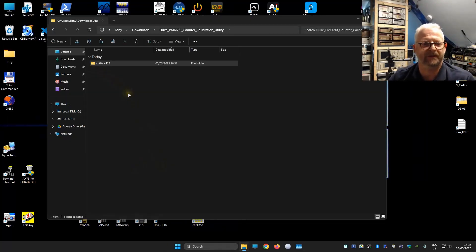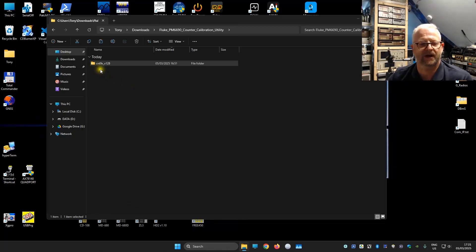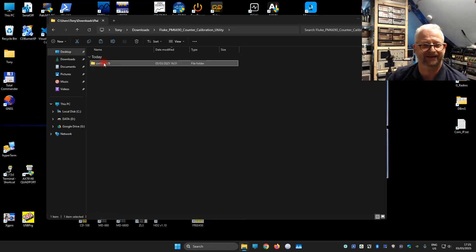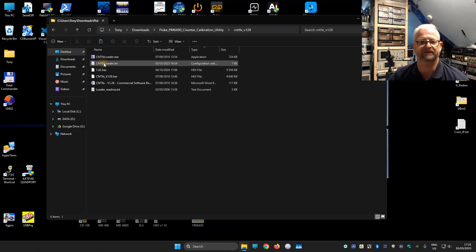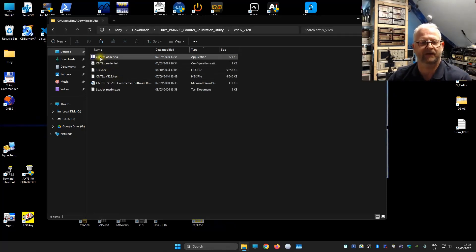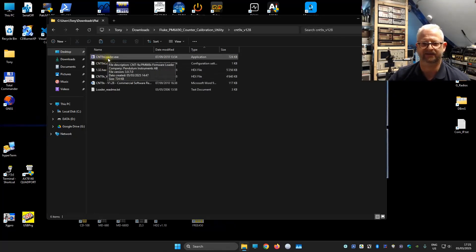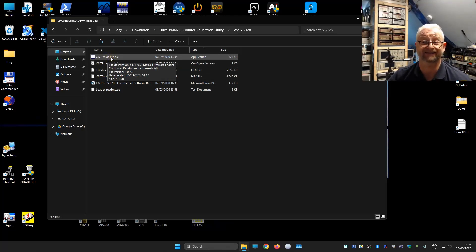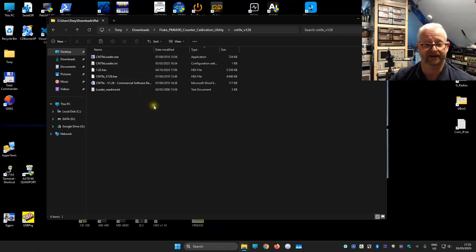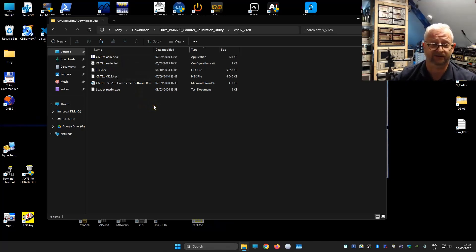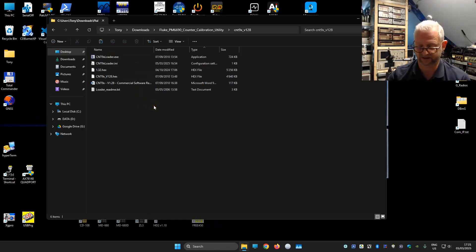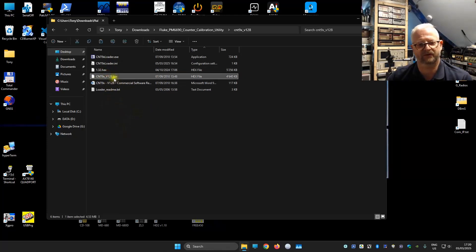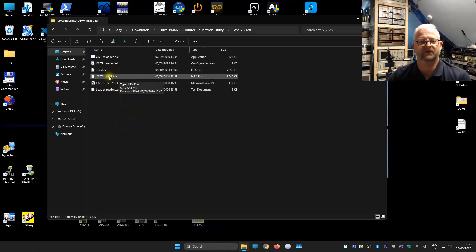To do the update I found the official program from Pendulum for the CNT-91. And it is the version 128. That is an official release. And I will be using that loader. I think that's the original manufacturer. And I already saw that it automatically detects that I have a Fluke. And probably if you have the Tektronix it will also automatically detect that. I come back later to that version. But first we update to the 128.